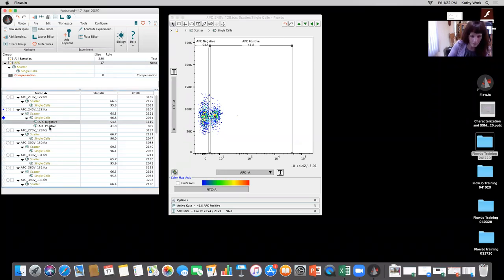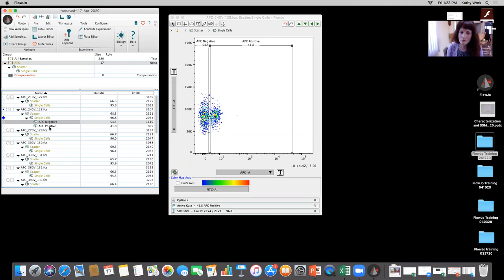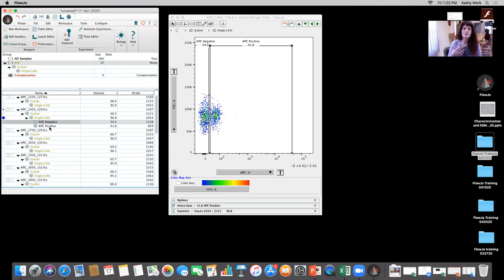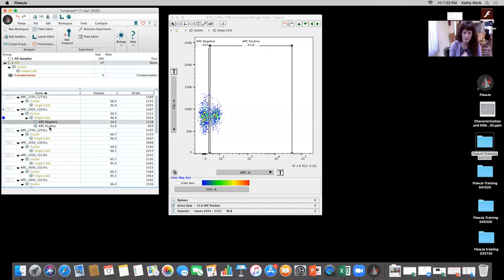Someone is asking what scale is measured on the actual cytometer to make sure all the scale transformations will work — specifically if it's in log or linear. Typically all fluorescent data for this characterization is going to be in log. When you're setting up for cell cycle or anything requiring a linear range, you're setting voltages with a control set. For cell cycle, you'd set the G1 peak in linear at about 50. For the purposes of this instrument characterization, we're doing it in log, because that's what most flow applications use.